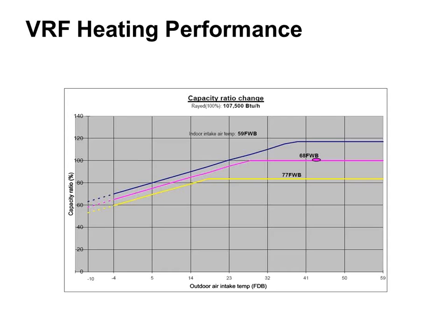In terms of the cold weather variable speed factor, which is what we're talking about today, this is what happens on VRF units, right? So on here I got 3 different lines, all with different indoor wet bulb temperatures. And for right now, I'm going to look at the 68-degree wet bulb because that's a typical design point. If you got 68 wet bulb, you probably got something in the low 70s for dry bulbs. That's a pretty common design point.